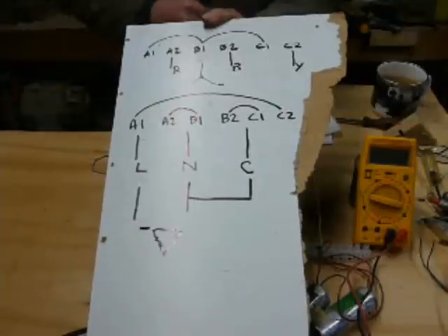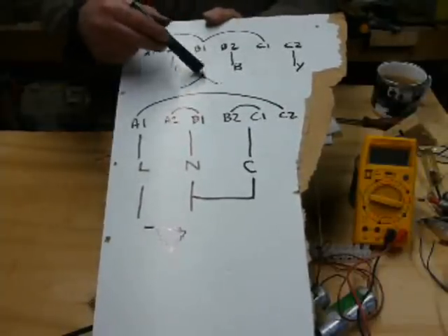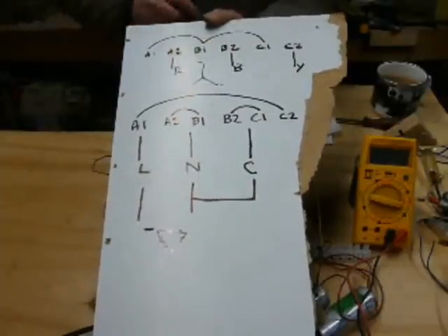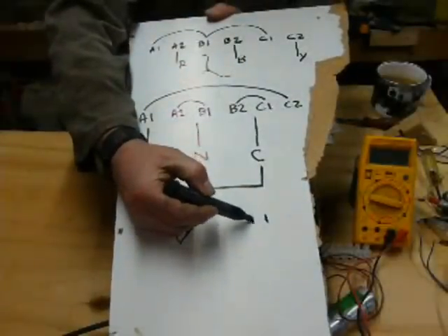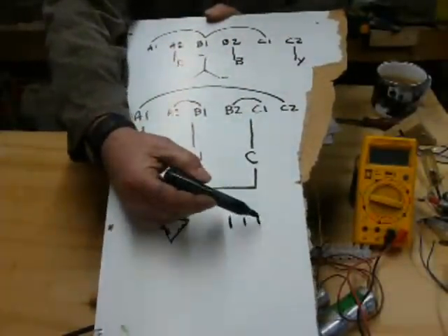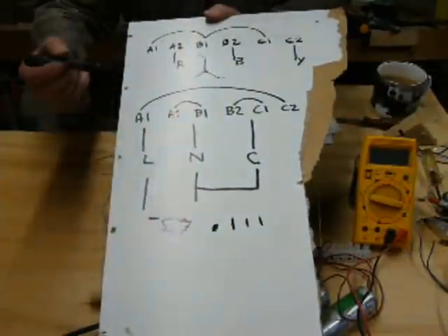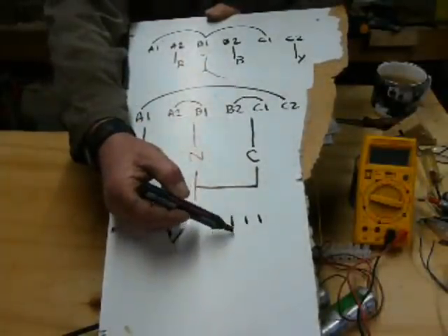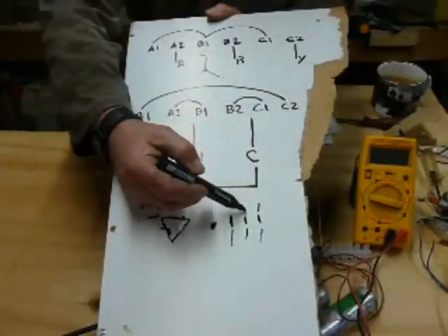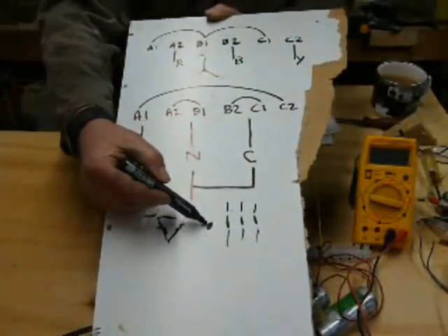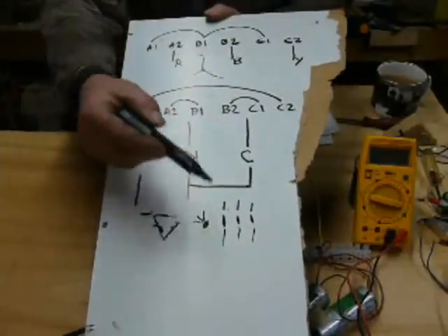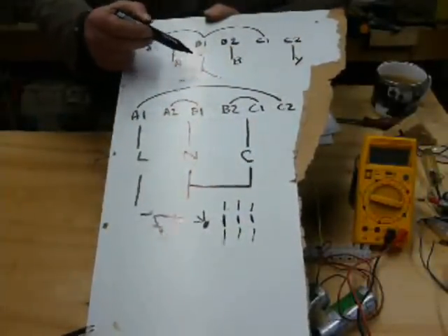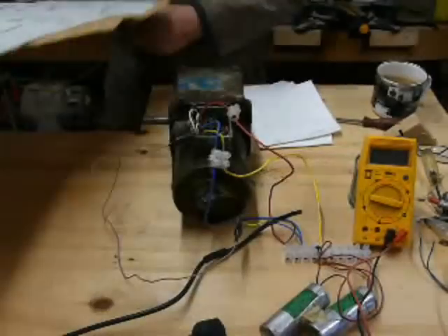So when you take a motor plate off and it's not what you expect, then just have a look and think. Go back to basics. How have they wired this? There was another motor I looked at a while ago and all it had was three connections with the blue, red, and yellow going to it, and then a further connection. And when I investigated, these had got the three wires in and they've got three wires going to the motor, and this one had got three wires going to it. So when you think about it, again, it's the same as that. It's wired in star.